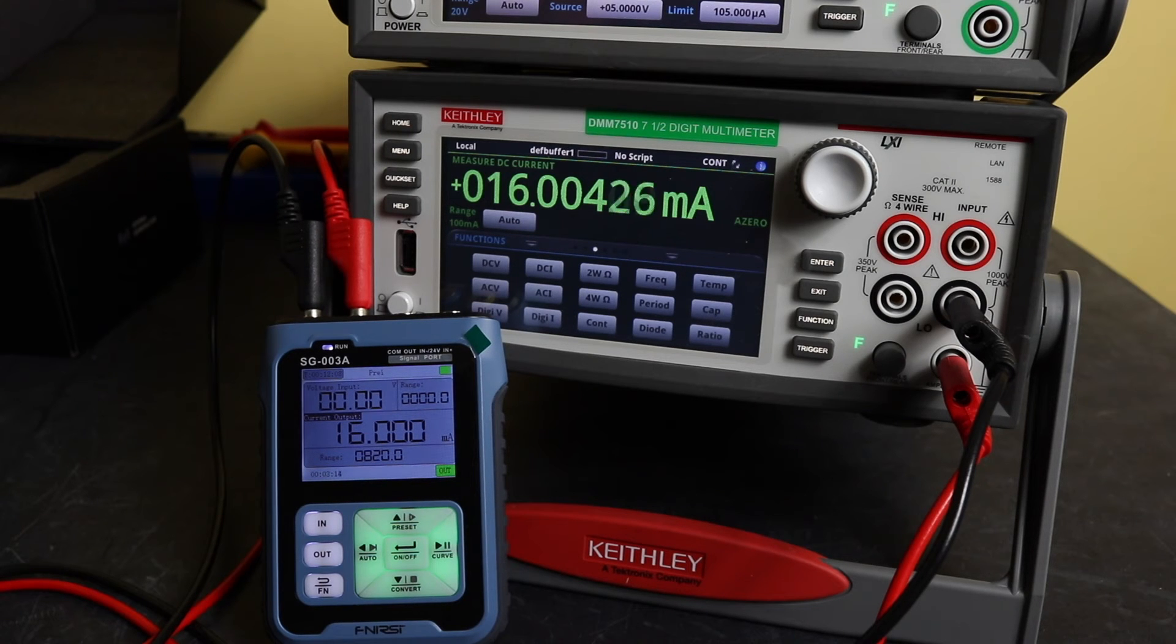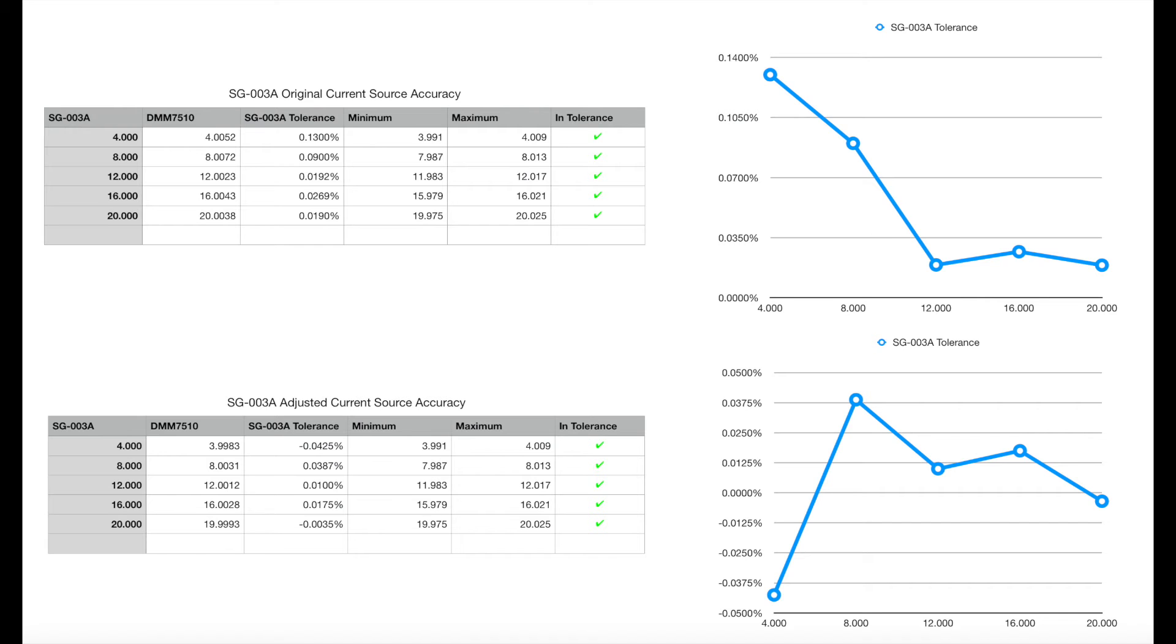But if you want the full range out of the instrument, I think you would probably struggle to get all the measurements within accuracy. It certainly seems much better sourcing when it does measurement mode. See, put the graphs up here for the source accuracy for current, you can see they are all in spec, no problems.